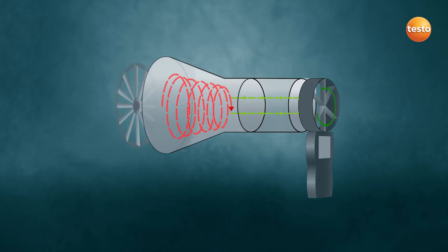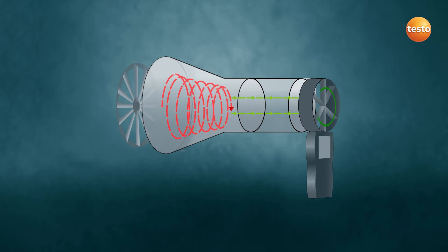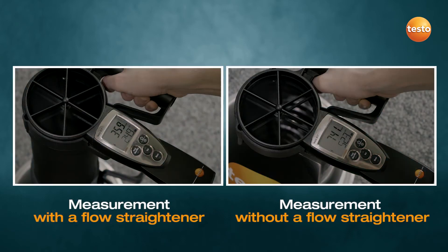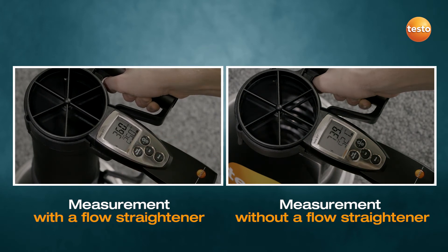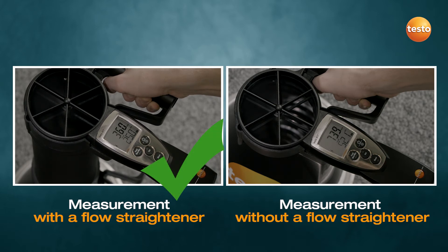What does the flow straightener do? With the patented testo 417 flow straightener, any rotational movement of the air is first calmed and changed to a straight flow direction. This directed airflow is then reliably recorded with the vane, so that the most accurate measurement results are achieved quickly and easily.